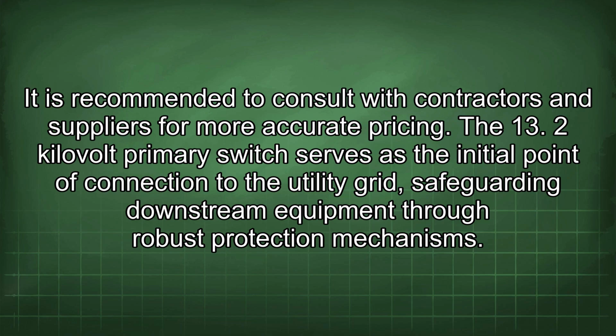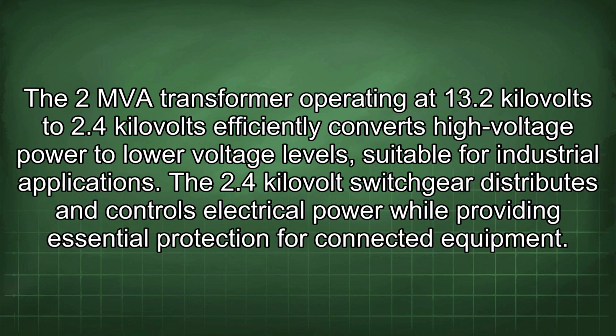The 13.2 kilovolt primary switch serves as the initial point of connection to the utility grid, safeguarding downstream equipment through robust protection mechanisms. The 2 MVA transformer operating at 13.2 kilovolts to 2.4 kilovolts efficiently converts high voltage power to low voltage levels suitable for industrial applications. The 2.4 kilovolt switchgear distributes and controls electrical power while providing essential protection for connected equipment.